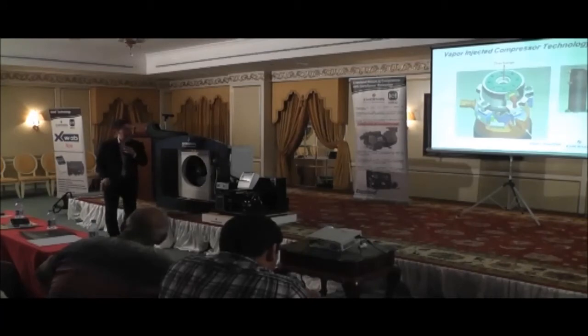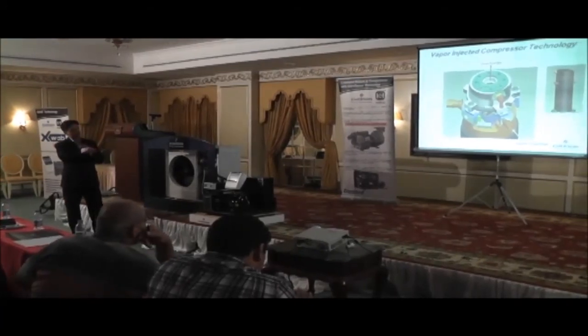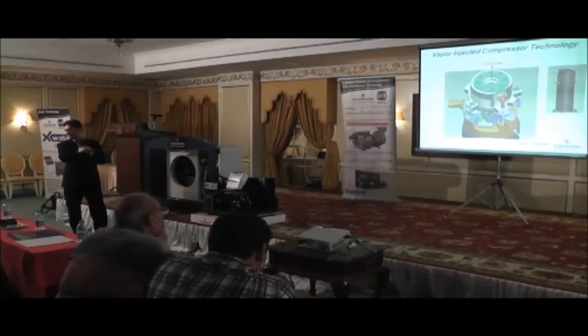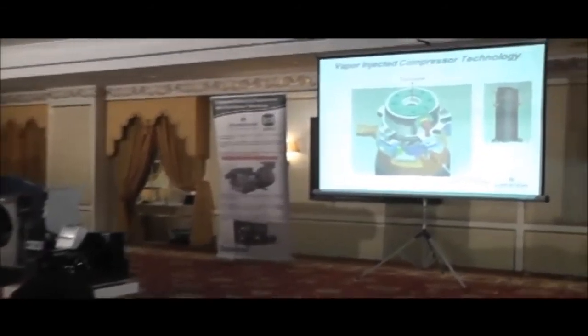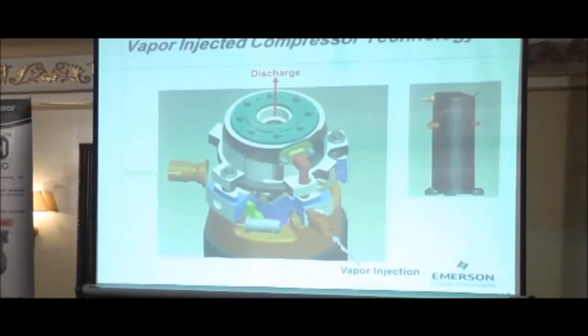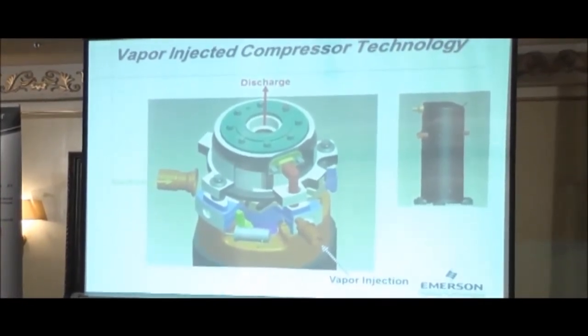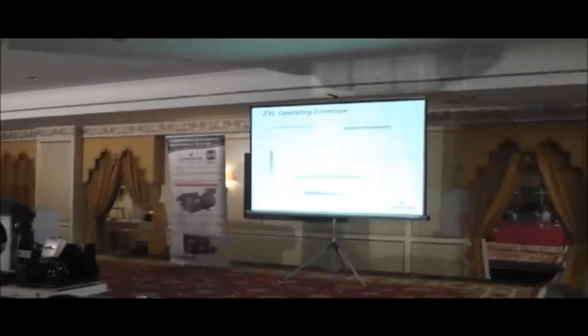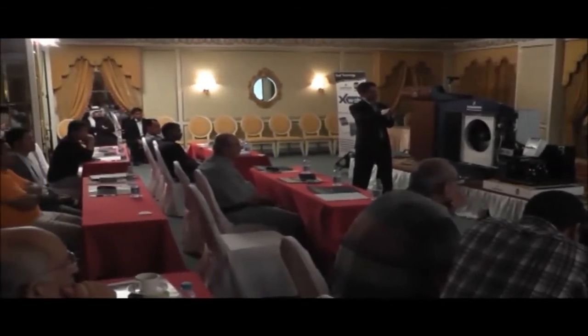So this is an example of the compressor. This is your main suction port, so this will come from your evaporator coil or your indoor coil. This is the secondary port which goes through the heat exchanger as a subcooler. That's going to be introduced into this port. And then the common discharge. So by using EVI, which provides cooling, we get a lot more capacity out of the system. This is the operating envelope. You can go from -40 to -15 up to 50 degrees C on R22. So it gives you a nice big operating envelope.